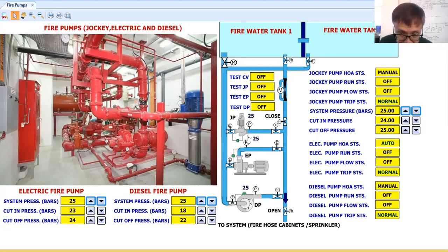After the maintenance, they have to open it again to make sure that when there is loss of pressure, the jockey pump will kick in. Likewise, the valves in the pumps, in the riser, and the control zone valves will be monitored by the fire alarm panel. So guys, this is how they do the testing and commissioning. They will close the main valve going to the system, then run the electric pump at zero flow, then 50% flow, then 100% flow. First the electric pump, then the diesel pump. The water will just be going back to the fire water tank. Now, I will show you some animation.